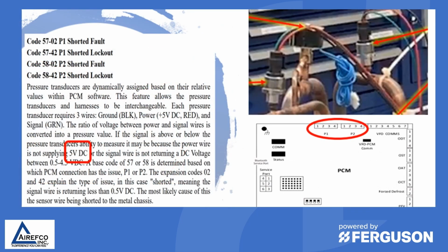Pressure transducers are dynamically assigned based on their relative values within the control board software. This feature allows the pressure transducers and harnesses to be interchangeable. Each pressure transducer requires three wires: the ground or black wire, the power, a 5-volt DC red wire, and the signal wire, which is green. The ratio of voltage between power and signal wires is converted into a pressure value. If the signal is above or below the pressure transducer's ability to measure, it may be because the power wire is not supplying 5 volts DC, or the signal wire is not returning a DC voltage between 0.5 and 4.5 volts DC.